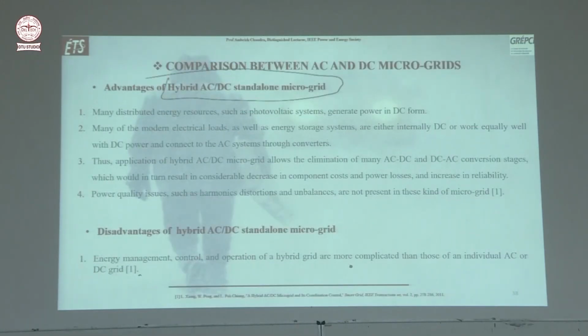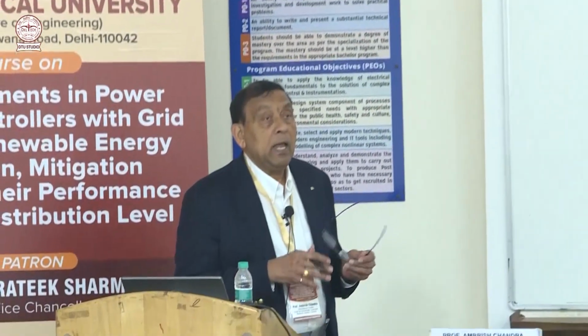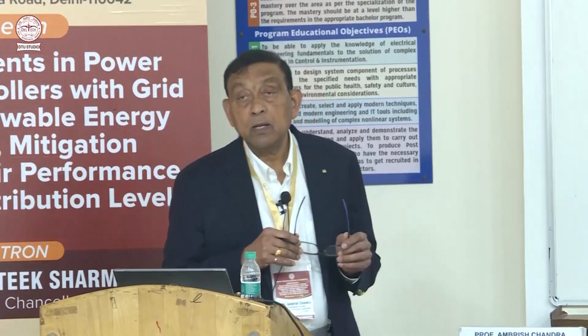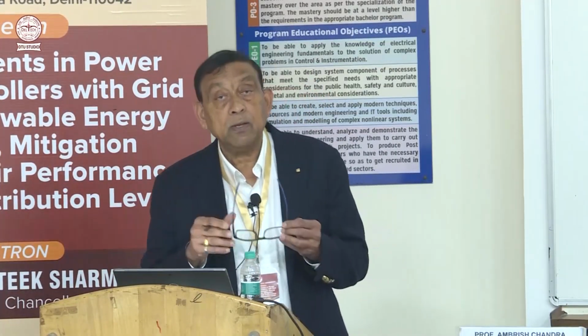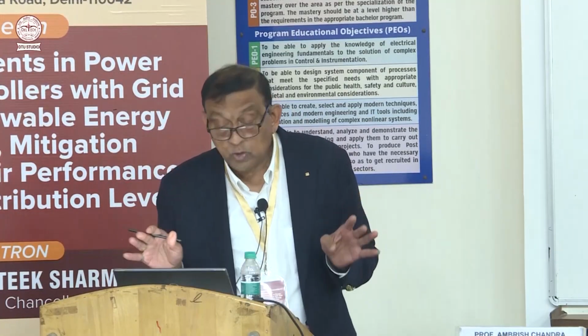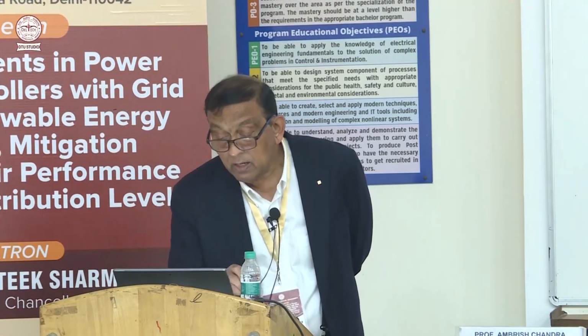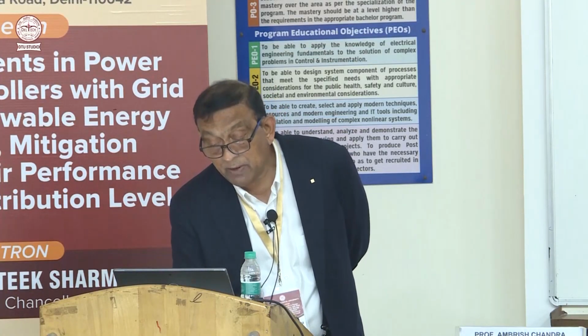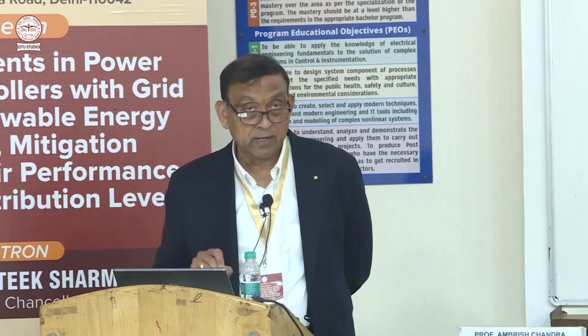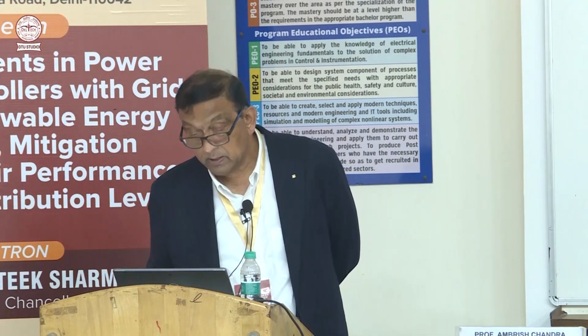In the same way, there are so many advantages of hybrid. That's why a lot of work is going on in hybrid AC-DC standalone microgrids. If you have an AC load or AC generator, you connect it to the AC grid. If you have a DC load or DC generator or batteries, or PV, you connect to the DC bus, and in between the two you have a bi-directional converter. So you can save a lot of money by saving a lot of power conversion. So it is more efficient. However, there are disadvantages of hybrid AC-DC, because energy management, control, and operation are more complicated in the hybrid system.